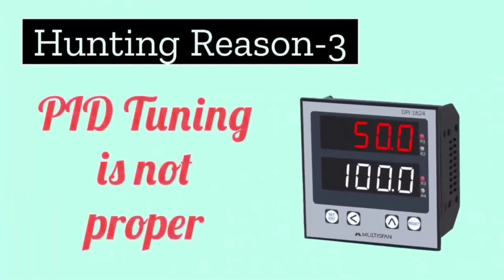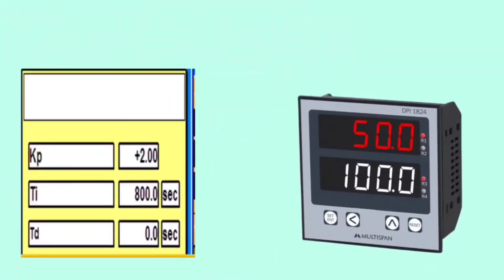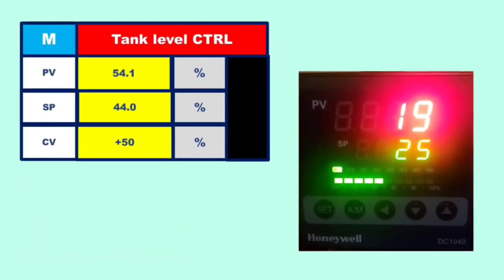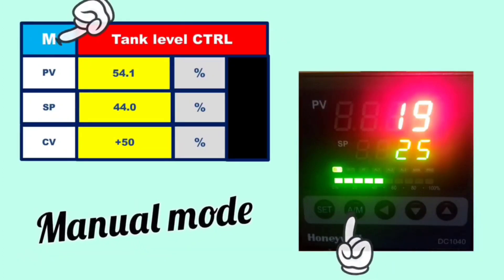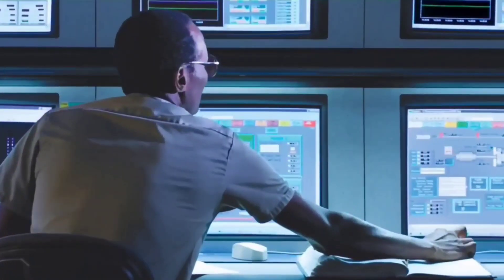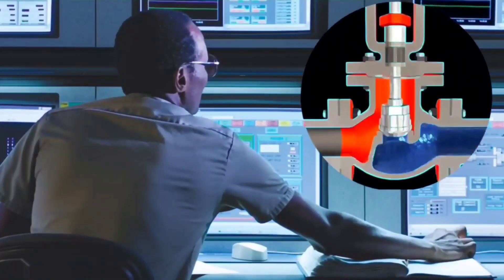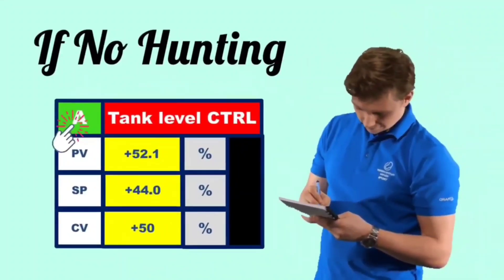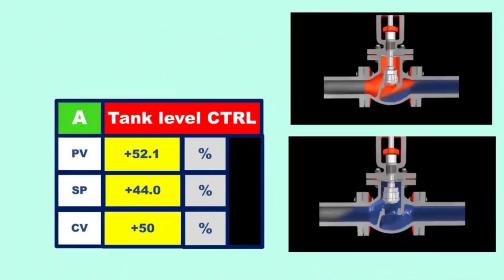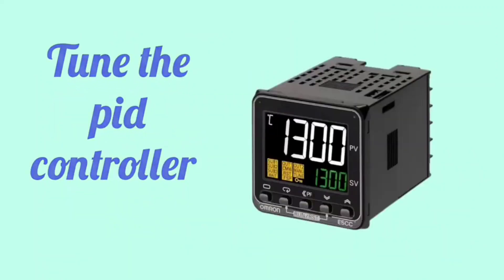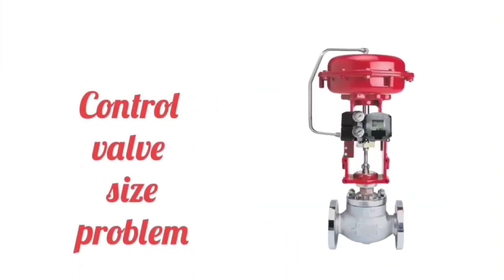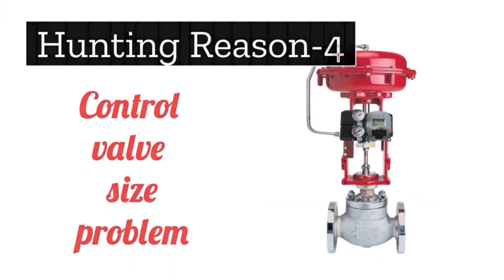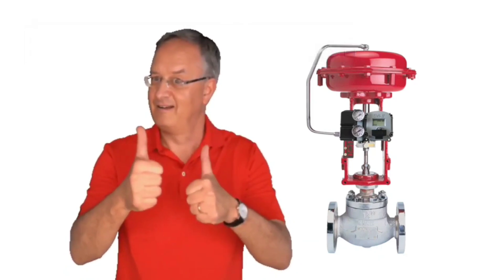The third reason for hunting may be that PID tuning is not proper. The problem of hunting can also arise due to improper tuning of the PID controller. To check this, operate your PID controller in manual mode and operate the control valve at different outputs. If there is no hunting in manual mode, then operate the control valve in auto mode — if hunting appears in auto mode, tune the PID controller. Also, if the control valve being used is not of the proper size, hunting problems can occur.